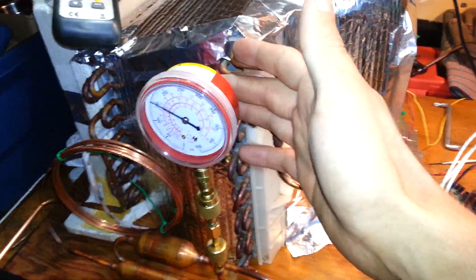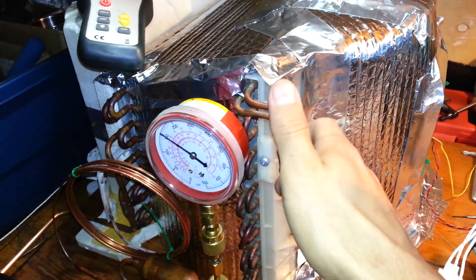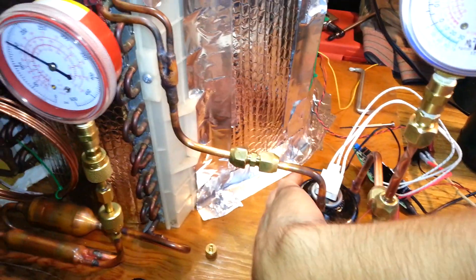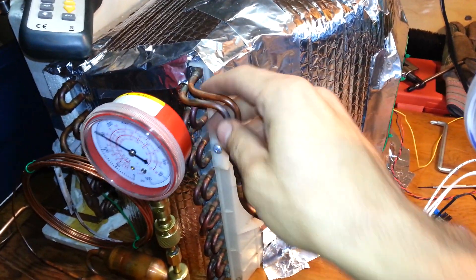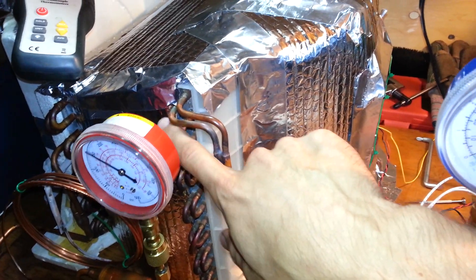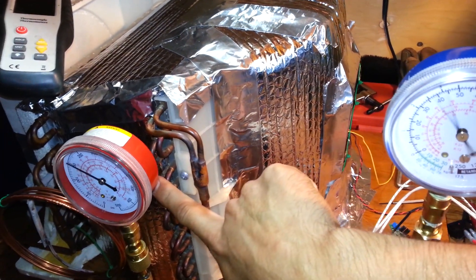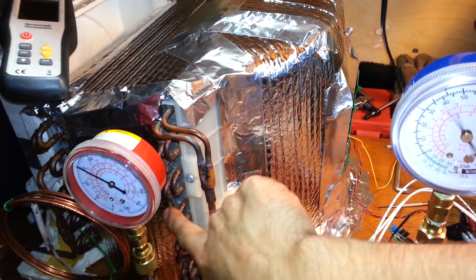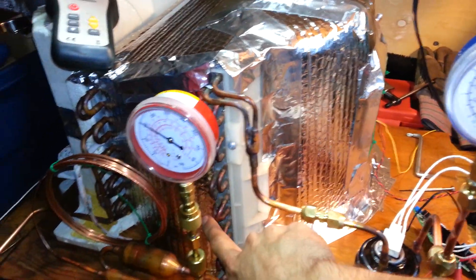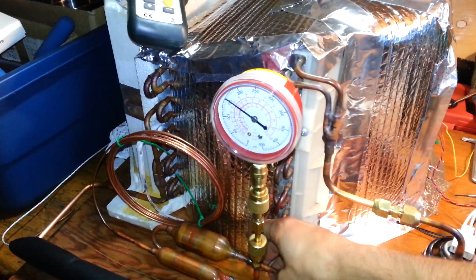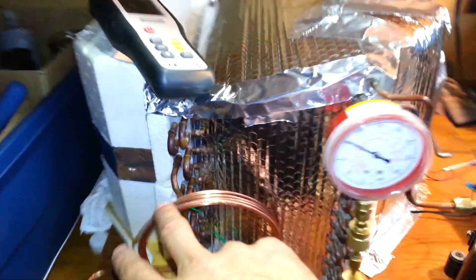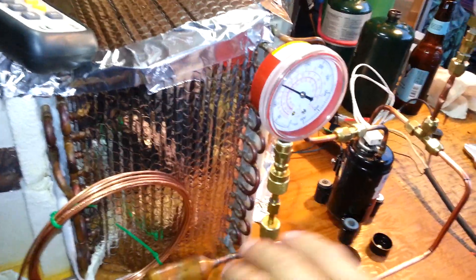And then on the condenser, we have a lot of discharge superheat. The compressor is pretty hot. First loop or two, it's warm, really hot. And then it really starts to cool off substantially to where about room temperature there.